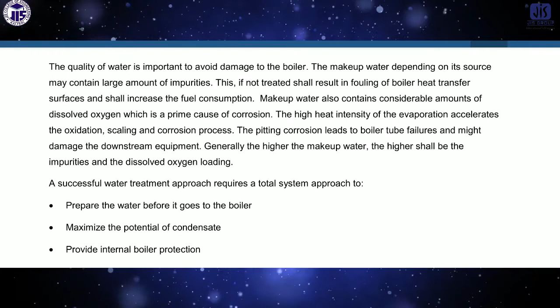Now we will discuss boiler water, its problem and the solution. The water which is used in the boiler is very important. Its quality is very important. Why? Because if we do not maintain the proper quality of the water, that means the parameters of the water, according to their limiting values, then different kinds of problems may arise. There may even be an explosion. So from that point of view, boiler water parameters are very important.